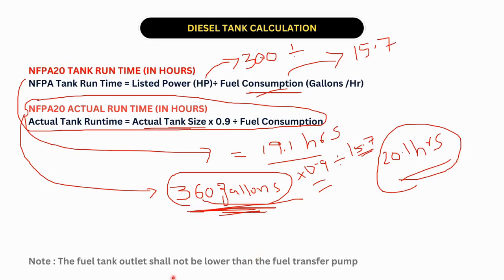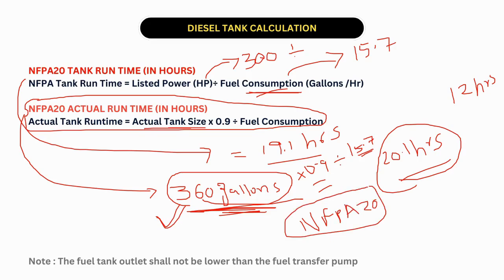As per NFPA 20, the requirement is only 12 hours, so our selected 360-gallon tank satisfies the NFPA 20 requirements. If someone asks whether a 300-gallon tank can be selected, you need to verify it complies with the two methods explained in the previous slides and decide whether it can be considered.